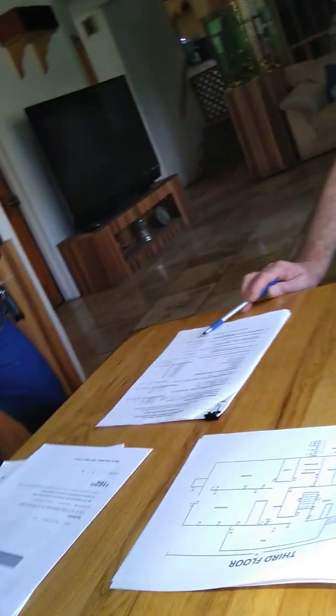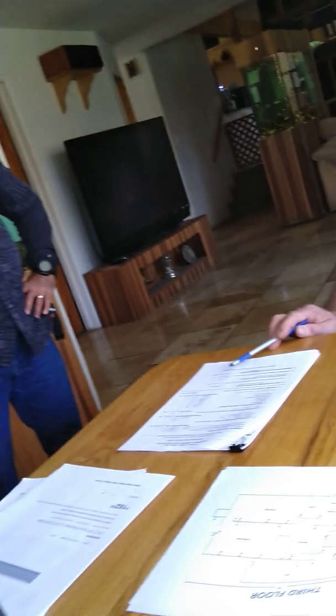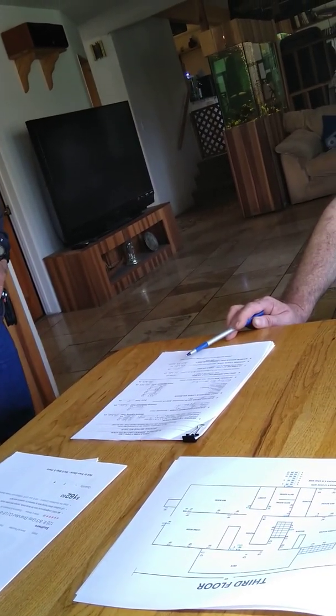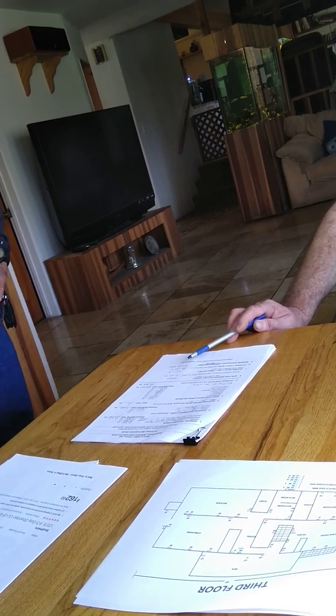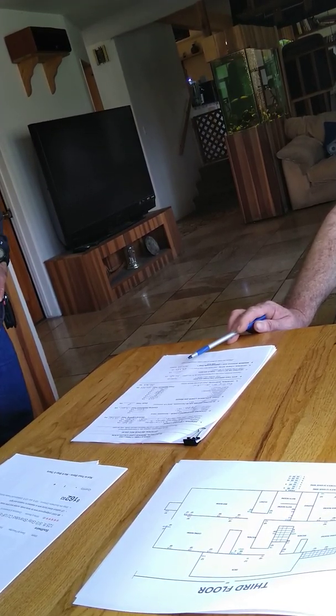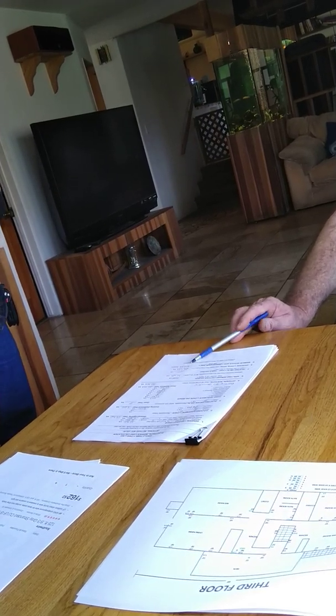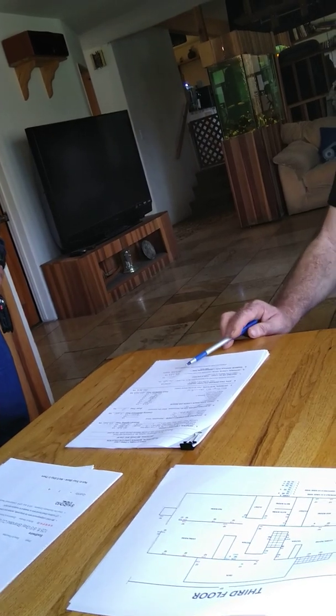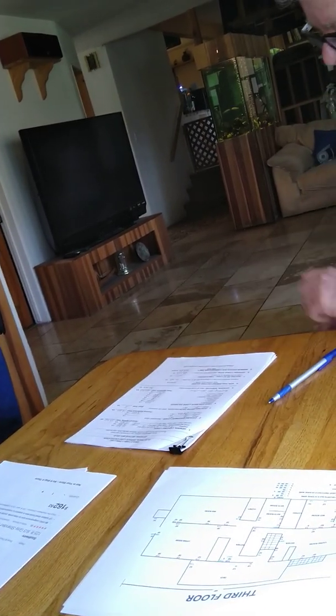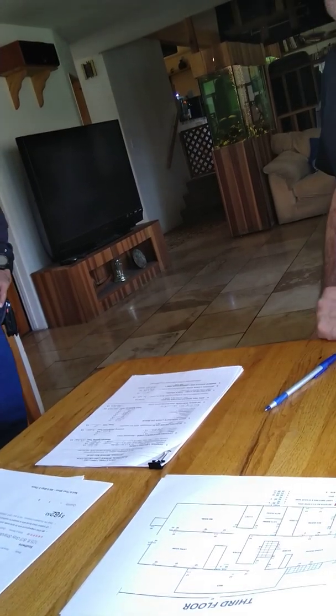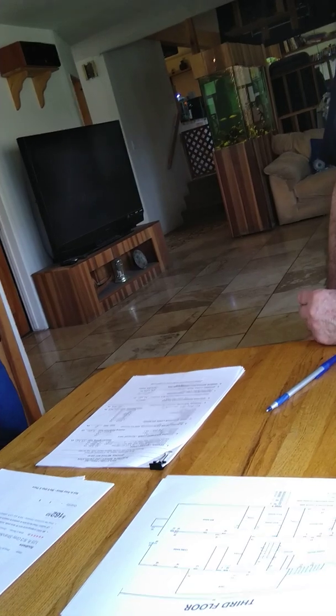If you're pulling 108 amps total, if you figured everything out correctly, and that panel down there is 200 amps, I might be able to multiply this by 0.75, which would put us down below 100 amps. Isn't a 100 ampere panel pretty much the standard? More and more people are going 125 and 200, and the reason is that a lot of people are putting in solar, and a lot of people have a lot of equipment, so 125 and 200 amps are what you see out there, but the minimum is 100 amps. Minimum 100. I've got quite a bunch of stuff running, so I wouldn't mind at all upgrading it just to have it. If it's not 200, if I were in your shoes, I would put it up to 200.